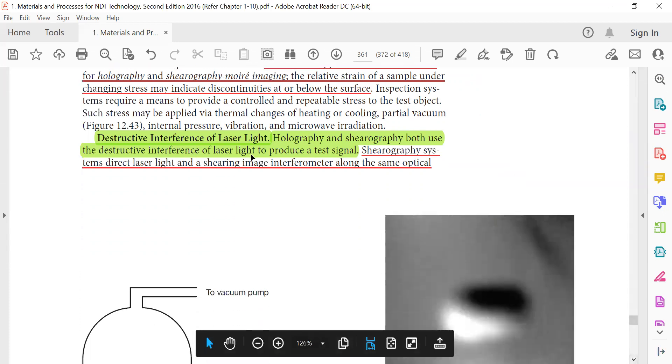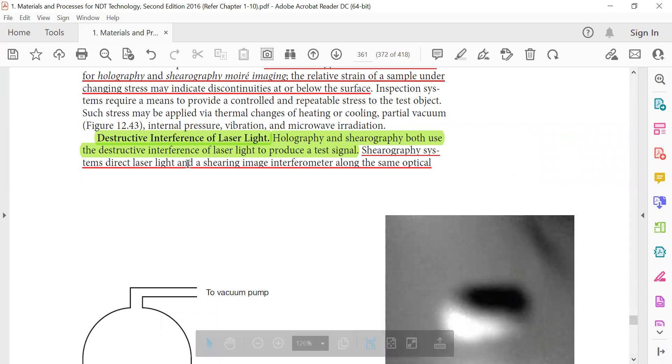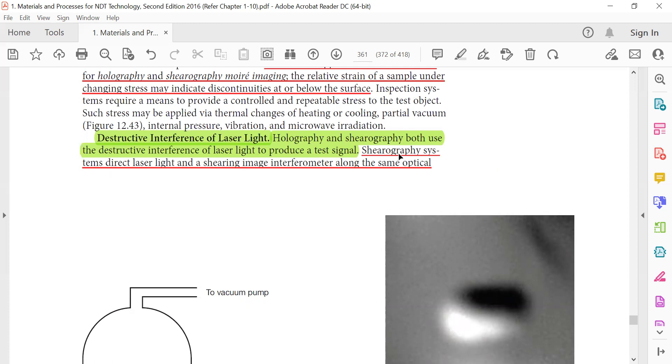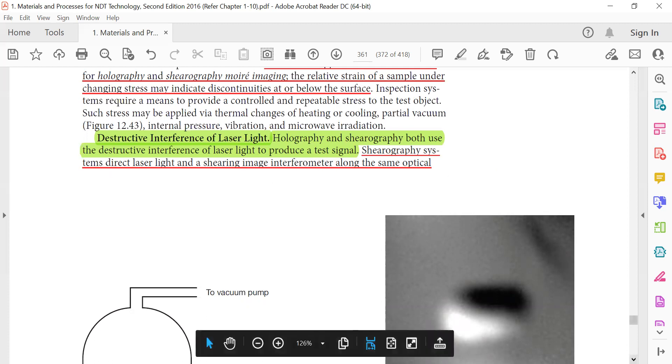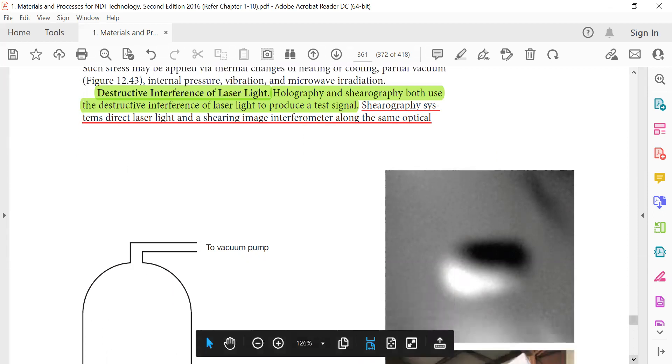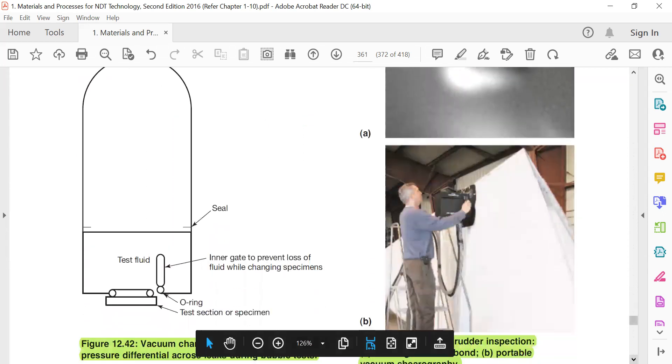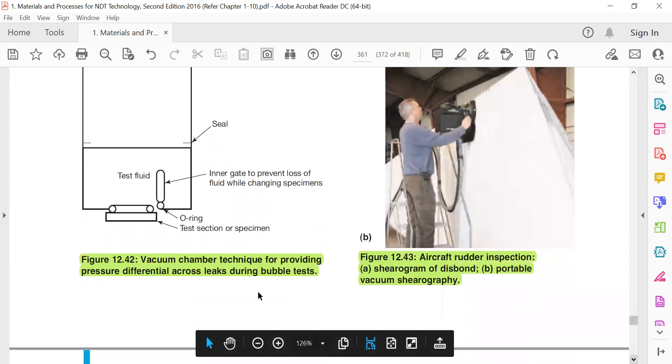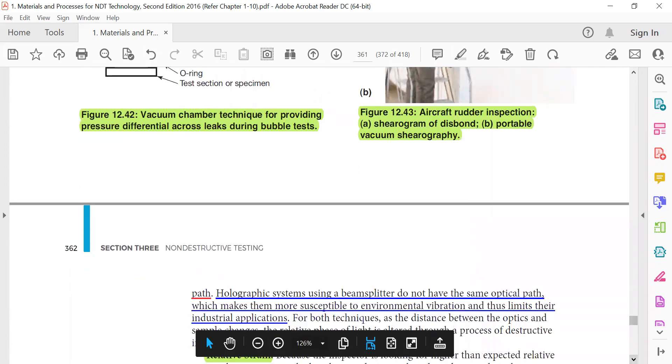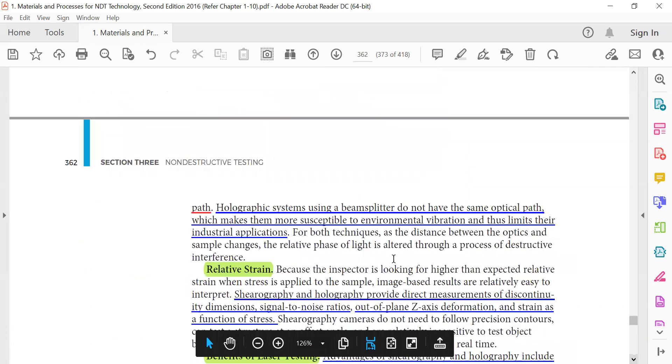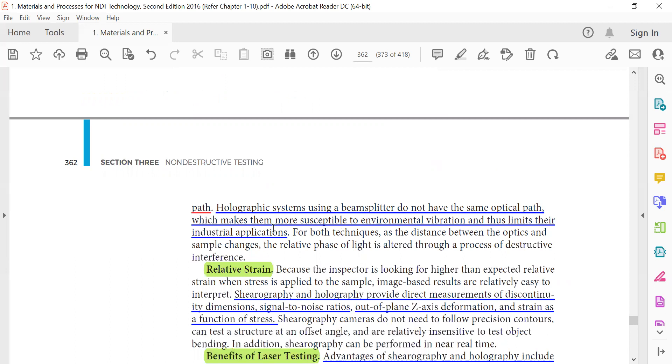Destructive interference of laser light: holography and shearography both use the destructive interference of laser light to produce a test signal. Serography systems direct laser light and a shearing image interferometer along the same optical path. Holographic systems using a beam splitter do not have the same optical path, which makes them more susceptible to environmental vibration and thus limits their industrial application.